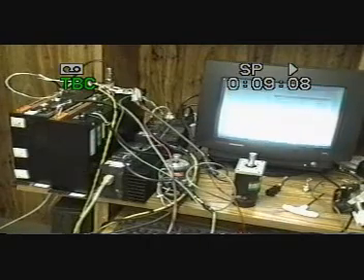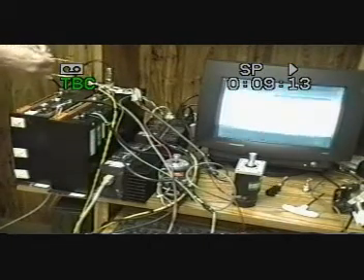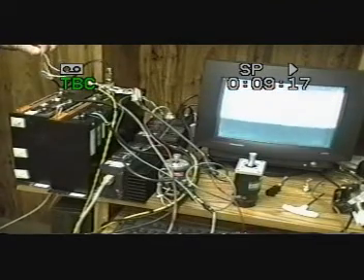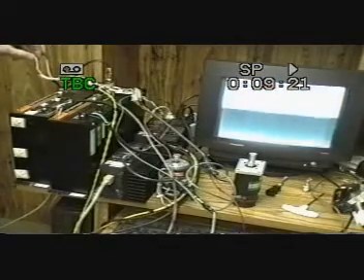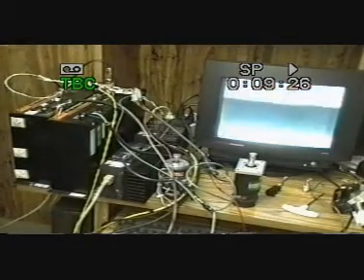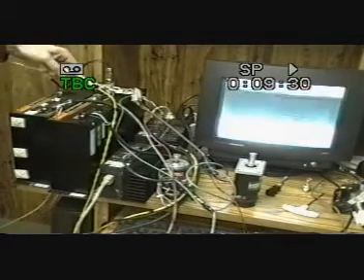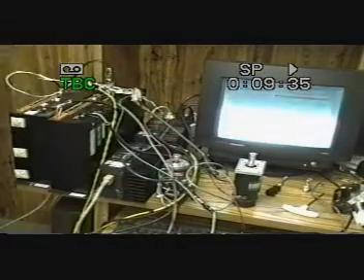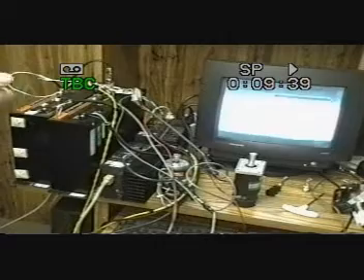I would encourage you to check the cable thoroughly. Make sure that you're using shielded twisted pairs. Very important to be shielded, very important to be twisted. I'm going to forward to Craig or one of you guys a document from another guy in an engineering forum that I'm a member of. A very good explanation of why we need the shielding, why we need the twisting to avoid EMI and capacitive coupling.